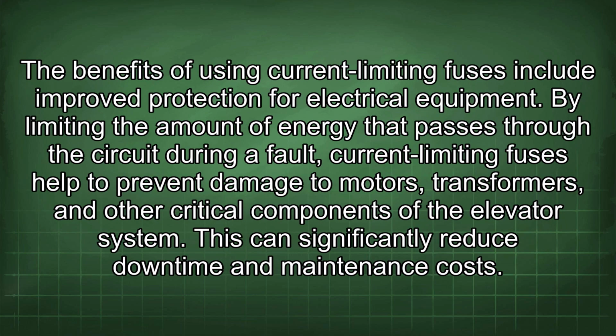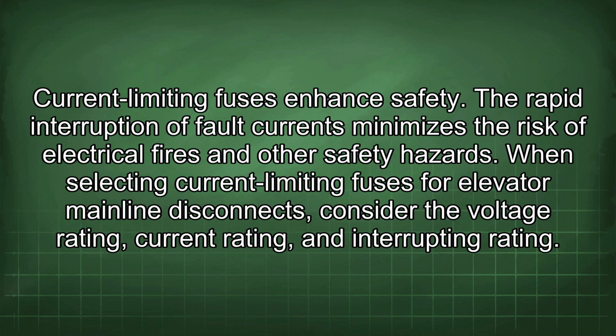The benefits of using current-limiting fuses include improved protection for electrical equipment. By limiting the amount of energy that passes through the circuit during a fault, current-limiting fuses help to prevent damage to motors, transformers, and other critical components of the elevator system. This can significantly reduce downtime and maintenance costs. Current-limiting fuses enhance safety. The rapid interruption of fault currents minimizes the risk of electrical fires and other safety hazards.